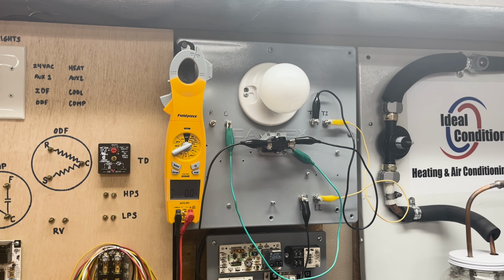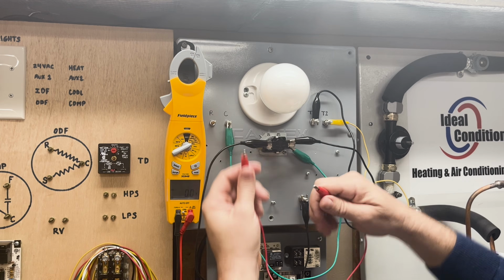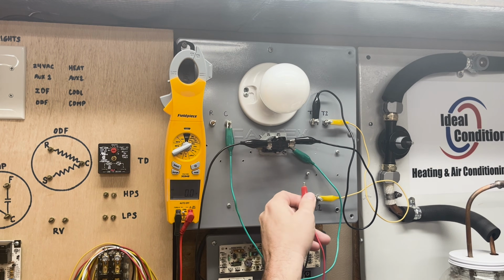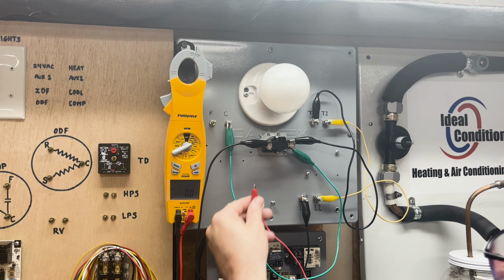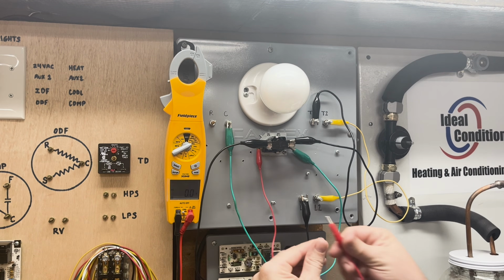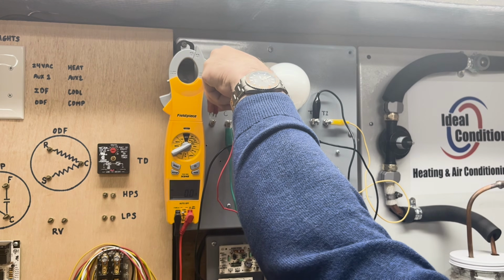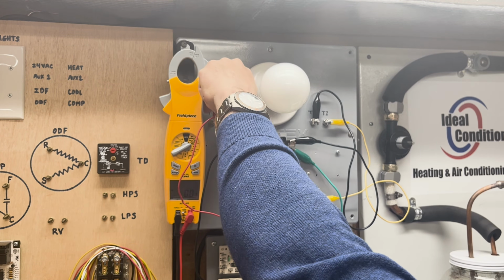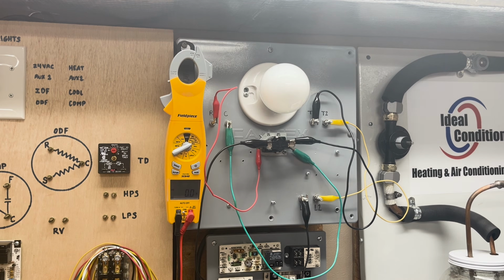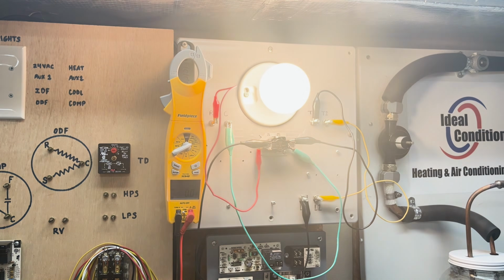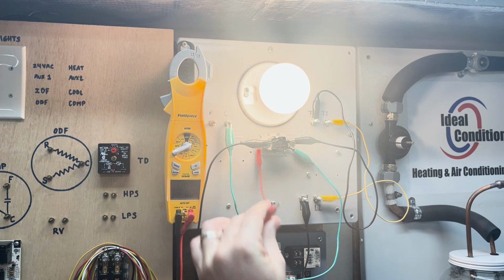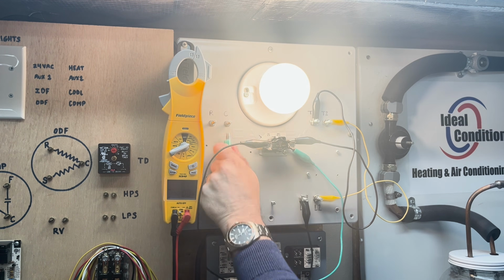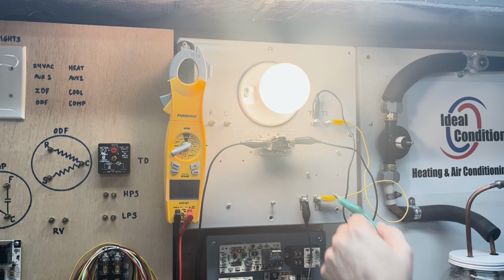It's one of the harder relays to do with live power, and try not to brush your knuckles past one of these bolts that have a full leg of power on it. I'm going to come up here to red, and we'll let the relay warm up again. And it was a little bit quicker on that side. So now we're going to go ahead and remove the 24 volts. And as you can see, the relay is starting to cool down, and eventually it will turn itself off.